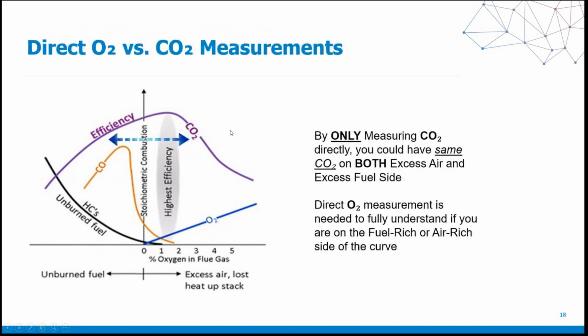And I'll further explain that here, where we look at direct O2 versus CO2 measurements. By only measuring CO2 directly, you can have the same CO2 on both the excess air and excess fuel sides. So if we look at this, CO2, as you see here, is a bell curve. And you can have the same amount of CO2 on both sides, whether you're on the air-rich side or the fuel-rich side, okay? That is why we need to take into account oxygen.